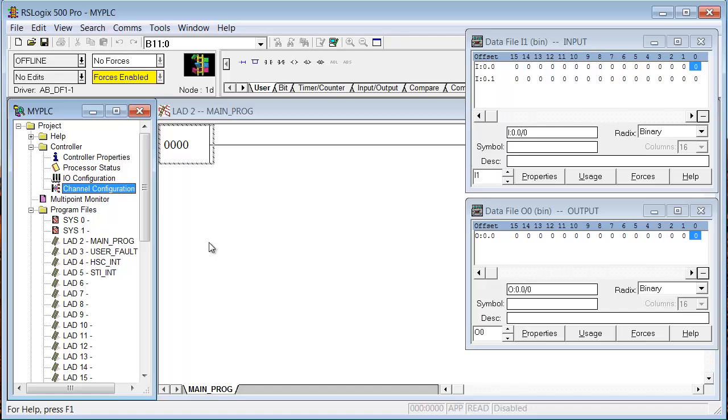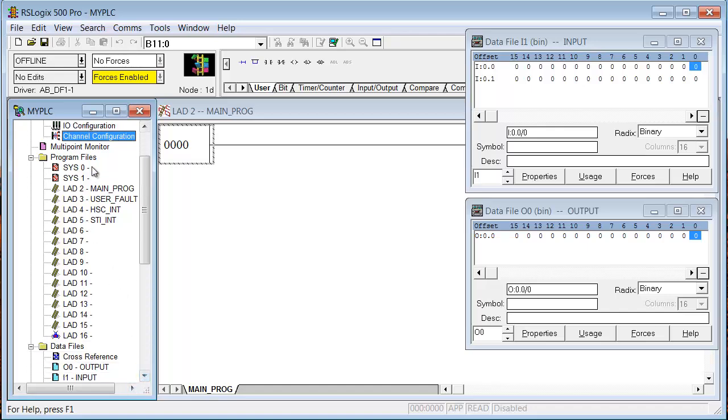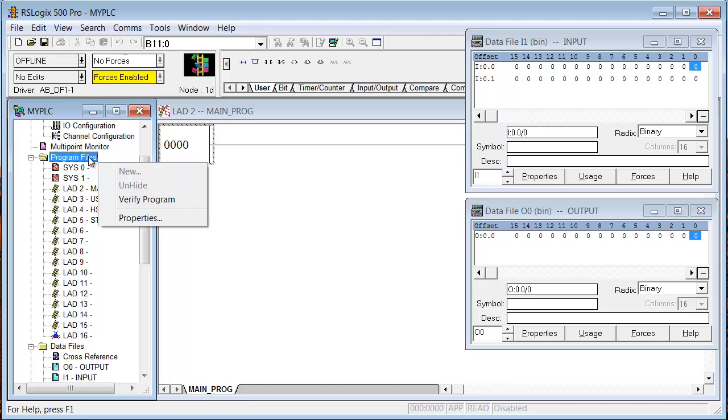So, when you go to download, you know, you configured your RSLinx driver to match the processor. So, RSLinx is configured at 9600. When you go to download, it's going to download it at 9600, but when the program gets down there, the processor is going to send back a complaint, and it's going to say, hey, you're downloading a baud rate that's different than the baud rate that this project is set for. Which do you want me to use? Well, typically, I would say, use what I download. In other words, overwrite what's in the processor. Then go back to RSLinx. Reconfigure, autoconfigure your driver. It's going to discover 19.2, 19,200 baud rate. And then you can go back online, and you're good. So, there's a number of different ways you can waltz to the end of the dance with RSLinx. Because this is a 1000, we really don't have any I.O. configuration or channel configuration.